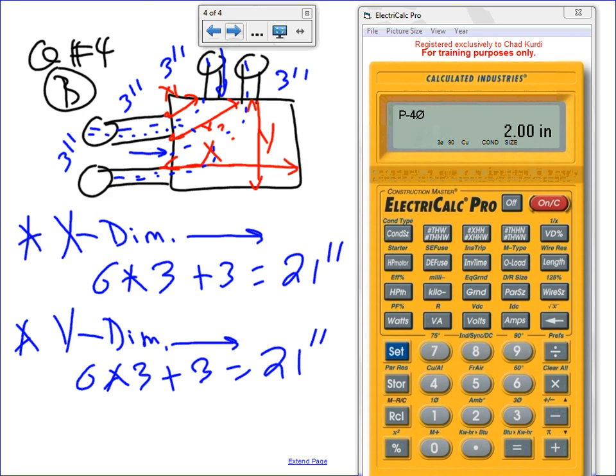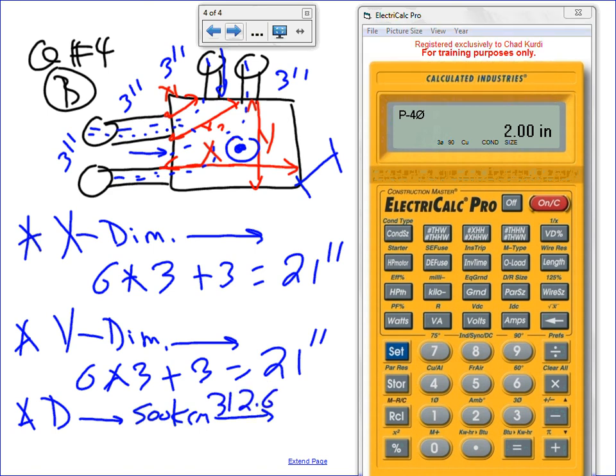This is for B. We didn't finish this one yet. The depth. I'm asking you the depth by giving you a conductor that's going to be sitting inside. What was the conductor? The conductor is 500 kcmil. So to find the depth, you take the 500 kcmil to Table 312.6(A), and that will give you, based on one terminal, number 6. Everybody knows how to find the depth.